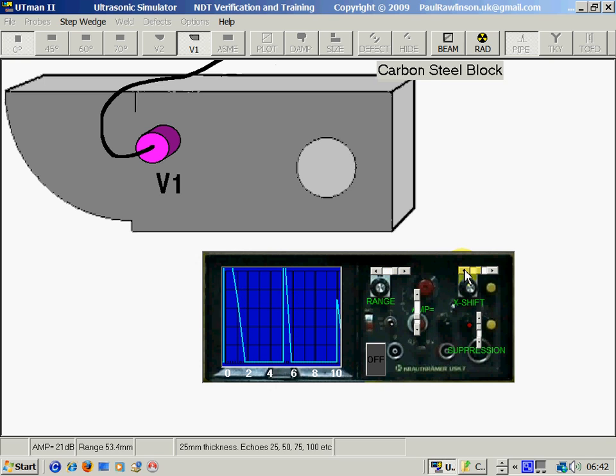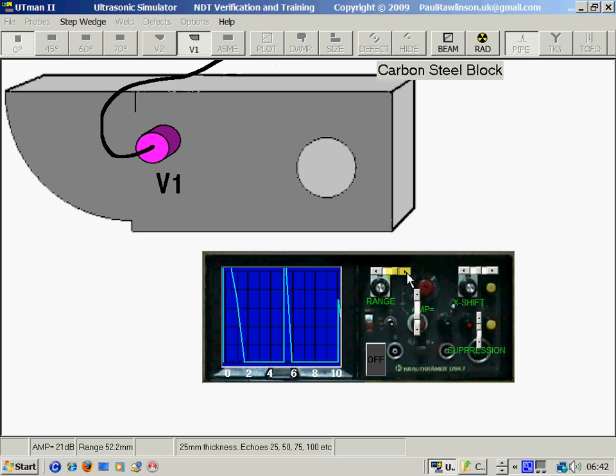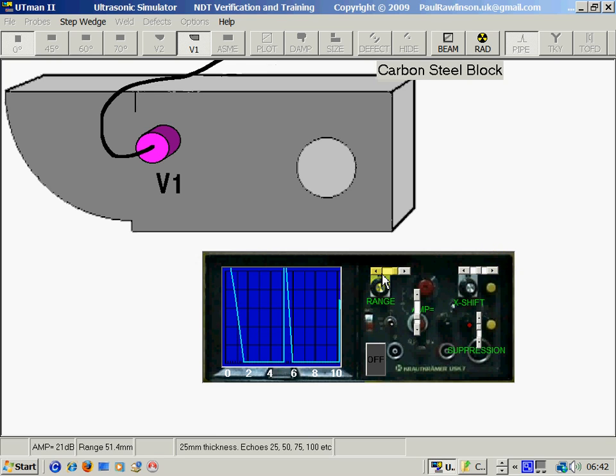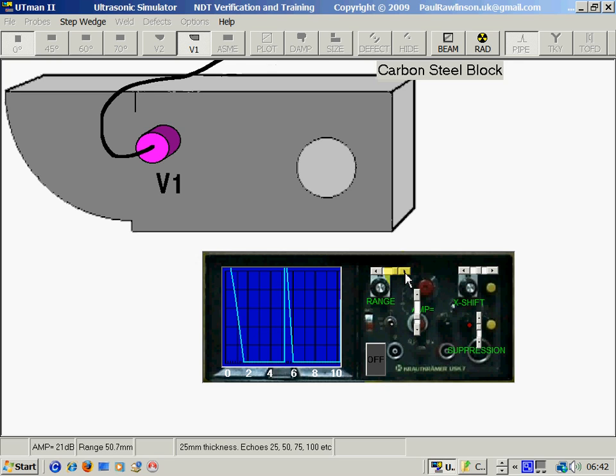Put the first echo in the center of the screen and the second echo at the end of the screen. So that is now calibrated for a total distance of 50mm.